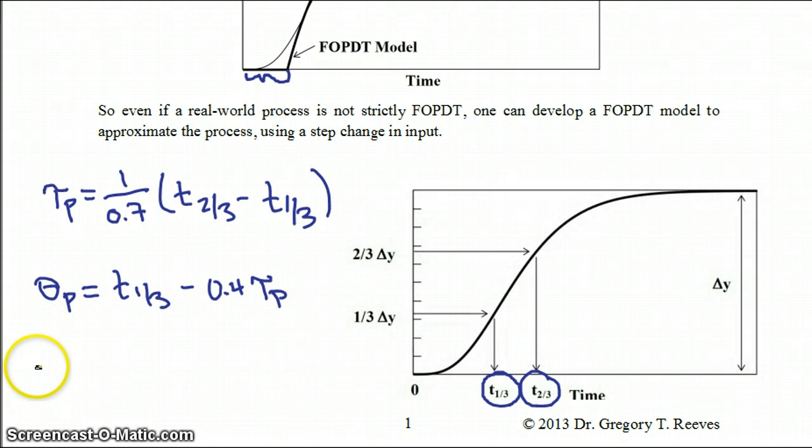Finally you need to know what your process gain is, and that's just as simple as how far does your new steady state deviate from your previous steady state divided by how much your step change in input was.